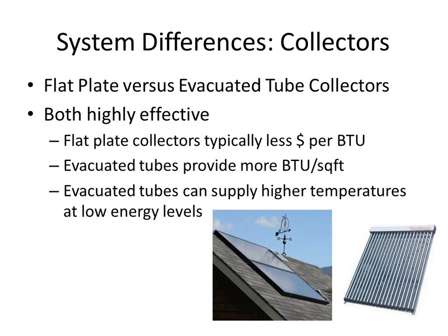The other factors to be considered, at least in the north, are snow shedding. The very properties that make evacuated tubes perform at higher temperatures, that almost absolute insulation between the hot absorber and the surface of the collector, mean that there's going to be no heat radiating to melt snow that accumulates on them. So in New England, that's a real factor. The fact that we do lose a little bit of heat from a flat plate collector in the wintertime is a real bonus.